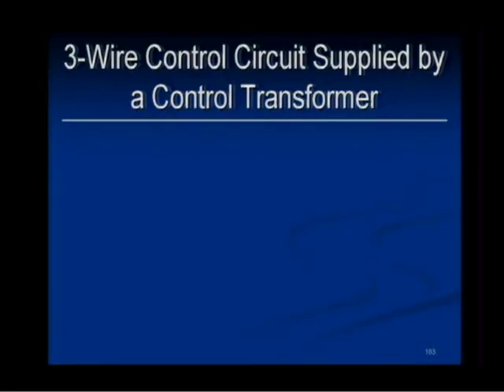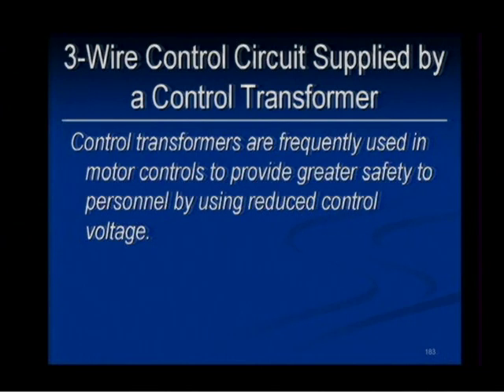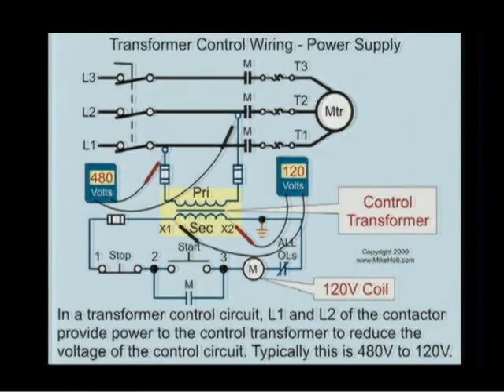All right. 3-wire control circuits. Another 3-wire control circuit. Oh, good, at least it's supplied by a transformer. Something different. Don't tell me you don't know 3-wire control circuits by now. Control transformers are frequently used in motor controls to provide greater safety to personnel by using reduced control voltage. All right, let's see what we got here.